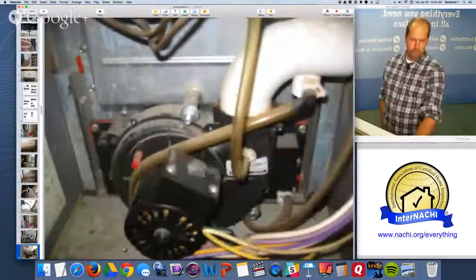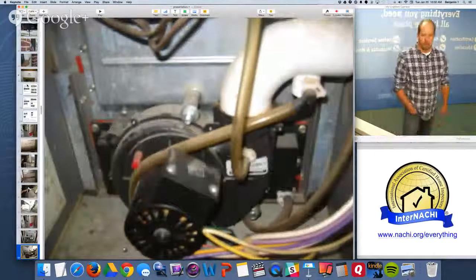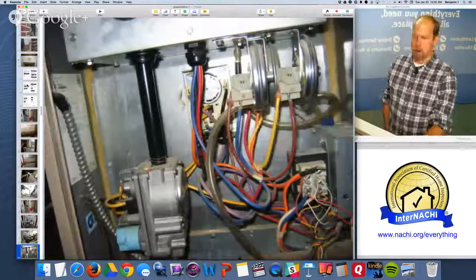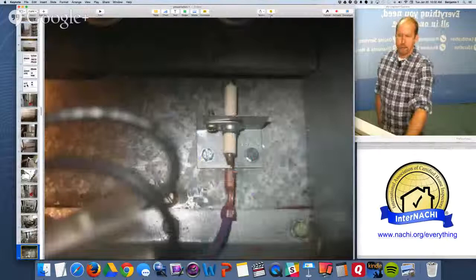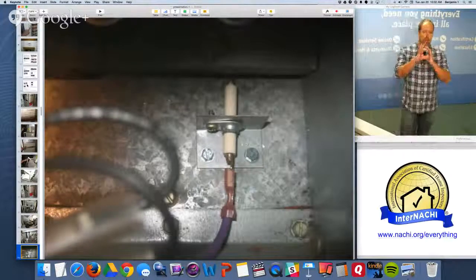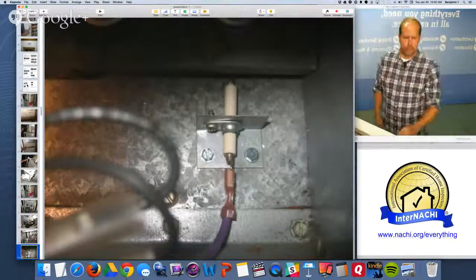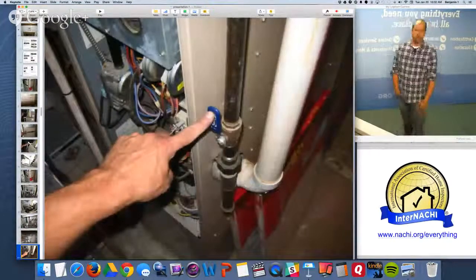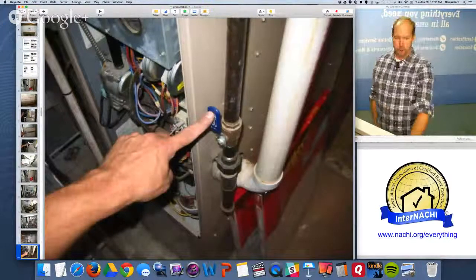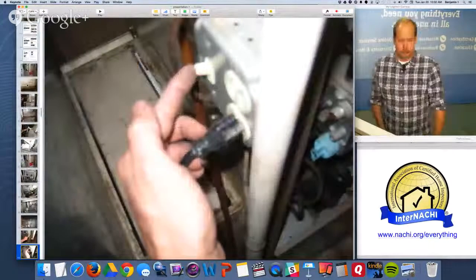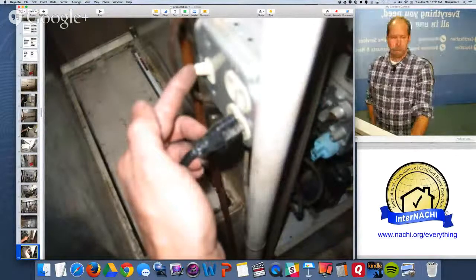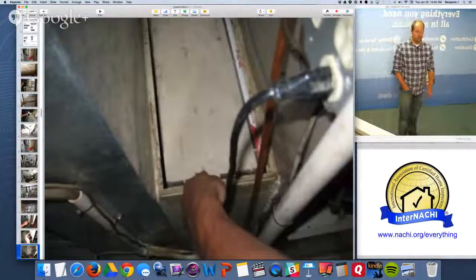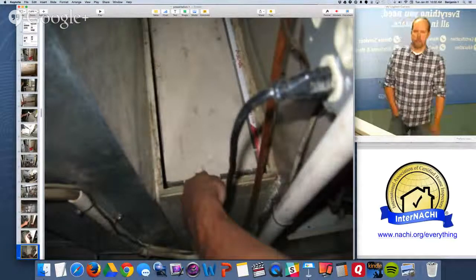With a sealed chamber and electric ignition for the pilot, I try to take pictures of everything — that's through the observation glass of the sealed chamber. I break it down into components: the gas shutoff valve, drip leg, the shutoff switch, the service switch. The sump pump is plugged in right there. And then there's the high-efficiency deep pleated media filter — the air filter on the cold air return of the ductwork.